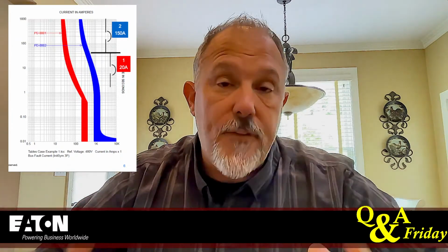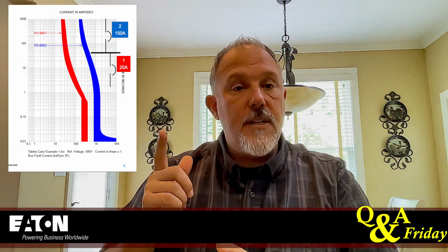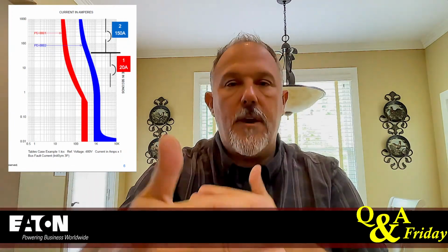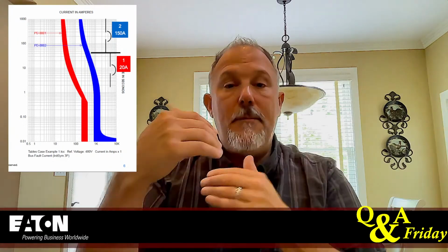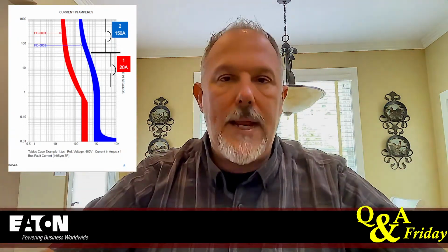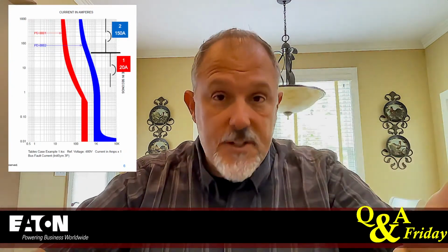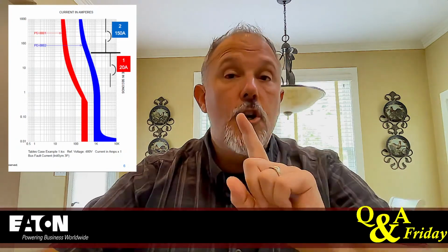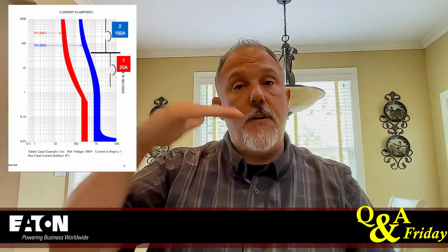The other thing you can do is reduce the fault current. Now, remember, the fault current is 5,000 amps. I want to get it down below 1,500 amps. One way I could do that is put a 1-to-1 isolation transformer in the picture. Now, that big hunk of iron core is going to knock that fault current way down. It does a couple things for you. It reduces incident energy for you.